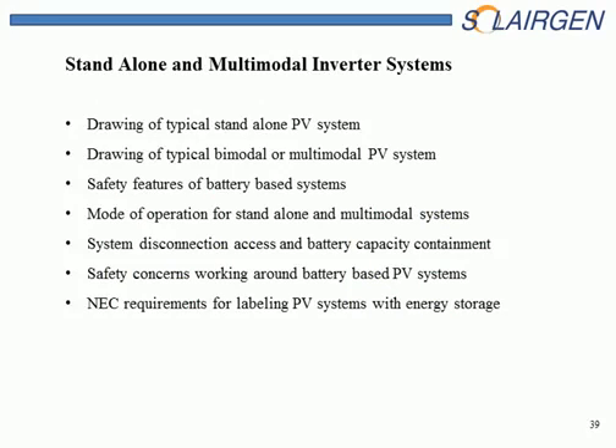Now let's take a look at standalone and multimodal inverter systems. These are not the dominant systems installed. Most of the systems you'll run into, if you run into one, will be an interactive system, but they're out there and they're going to become more common. The good thing is the ones that are being installed in the future have more labeling and are safer, so they function in a friendlier way to first responders. The older systems, not so much. So I want to go over all these aspects of standalone and multimodal inverter systems and what you should be looking for out there.